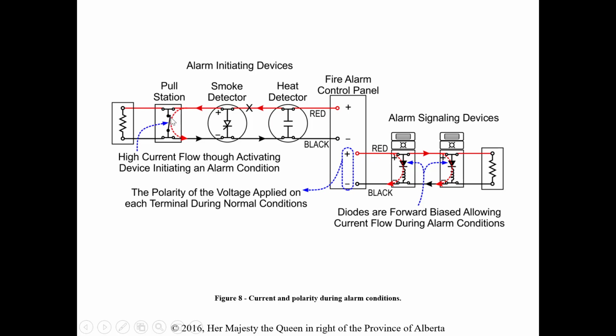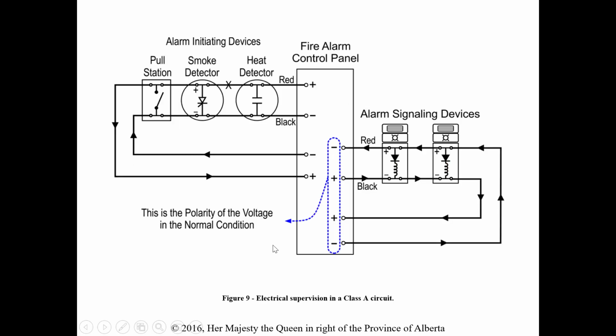Again, here we have a pull station that's been pulled. Now we have a path through the pull station, not through the end-of-line resistor anymore. That's going to put the control panel into an alarm condition because there's a different value of current associated with that. We won't see the current that we saw going through the resistor. It could be a smoke or heat detector, but in this case it's the pull station, so we have a path through there. Then the panel switches the polarity because it's an alarm condition, which forward biases these diodes and signals any device attached to that circuit. But again, the big thing with Class B is that it has an end-of-line resistor, and if we have a break, we lose everything on the other side of that break.